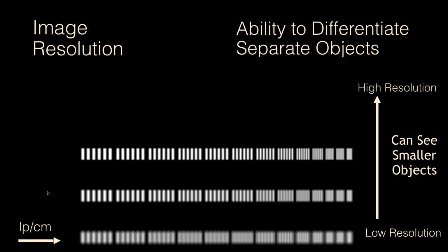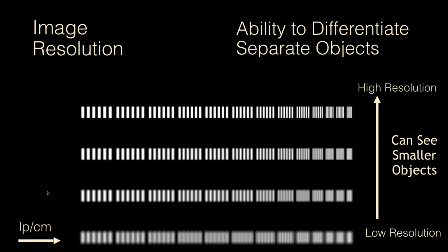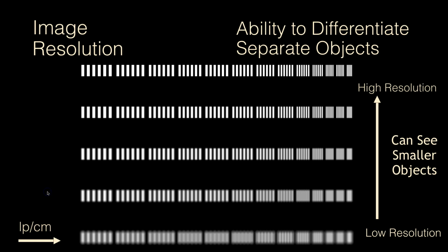So as I go up to these higher levels of resolution, I note that in each of these cases, we have the same number of pixels that we're showing. So we're showing the same number of pixels in this matrix as we're showing in this matrix. But this has the extreme high resolution, and then this has the lower resolution, because we're not always limited by the number of pixels that we're showing. We could be limited, for instance, in the case of CT, by the size of the focal spot and the size of the detector.